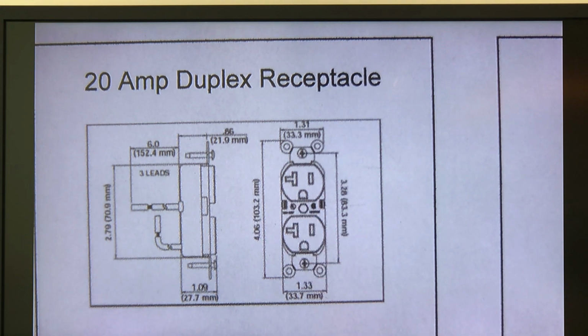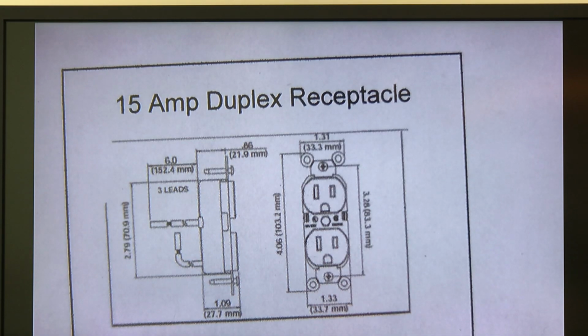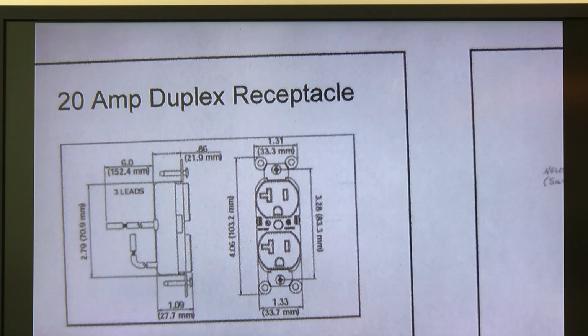The reason for that is that if you have a 15 amp power cord, it will plug into a 20 amp receptacle and everything will be fine. On the other hand, if you have a device that requires 20 amperes, you cannot plug it into a 15 amp rated outlet. So it's a safety device, completely passive thing. But the idea is so that you won't overload the branch circuit. In all other respects, everything between the two is the same. So you have here 15 amps as a straight blade, and over here you have a T-shaped neutral for a 20 amp duplex receptacle.